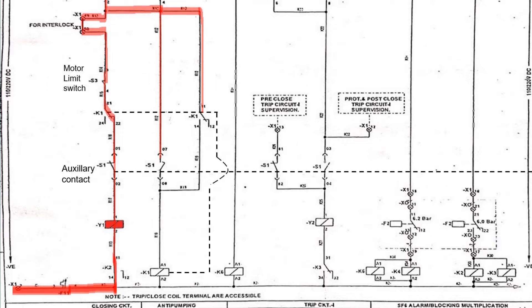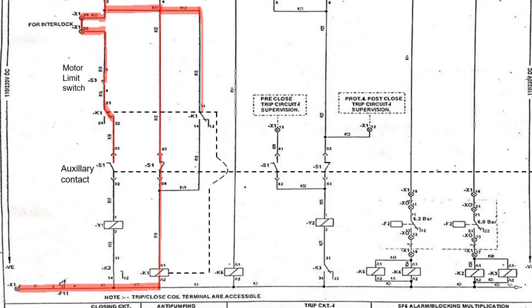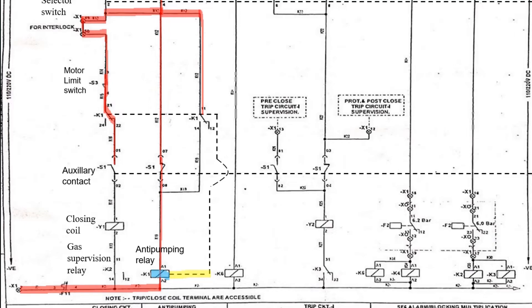As soon as the circuit breaker closes, the auxiliary contacts S1 operate and change their position — that is, all NO turns to NC and NC to NO. So the current to the closing coil gets cut and it gets de-energized. Simultaneously, K1 anti-pumping relay is energized and the contacts of the anti-pumping relay change their position — NO contact becomes NC and NC contact turns to NO — forming a closed circuit on the right-hand side and freewheeling the current after the close operation.